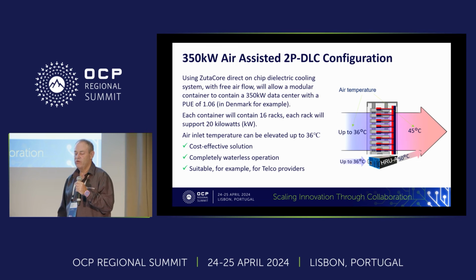And then when we're using the direct-on-chip liquid cooling with air assistance, we see that we actually get to a PUE of 1.06. And we see that this kind of solution is not only efficient in energy, it's very efficient in cost. This is a very low-cost solution for a 350 kilowatt data center that has minimum facility for cooling. You see only the air-assisted and the direct-on-chip liquid cooling. No other facility is needed here. So it's cost-effective, and it's a completely waterless solution. It's important for some of the market, and it's suitable for telco and, as I said, in neighborhoods. There is no real way of reusing the heat here, because the heat is moving out as hot air from the data center.